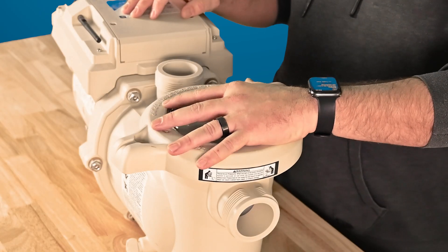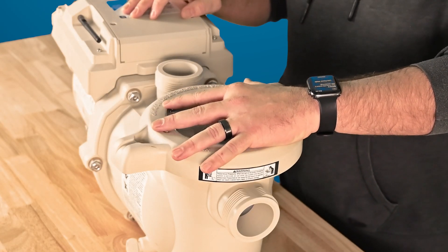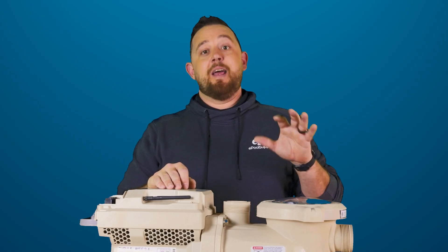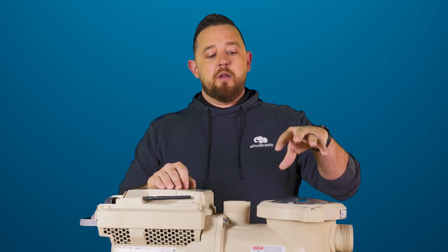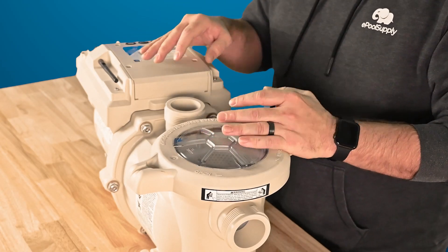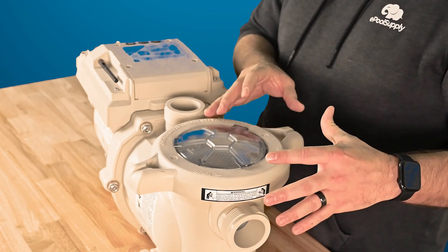You'll notice on the front you've got a much bigger volute, which is actually nicer comparatively to the old SuperFlo style. This is going to allow you guys to get some more debris in there — it's an actual better pump. I would definitely recommend this one over the older version when you're looking for that horse and a half, just for that front wet end portion of it.